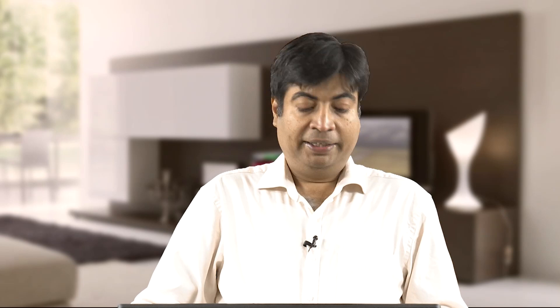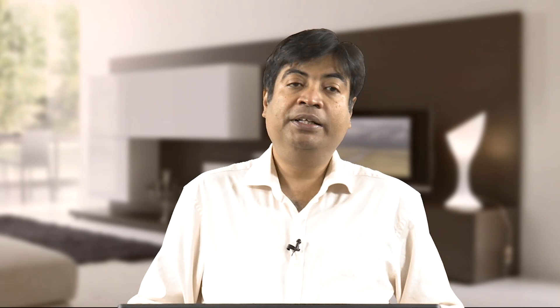The next important aspect of DC microgrid is controllable generation, which provides stable and necessary levels of voltage and frequency. In an AC or hybrid system, frequency must be maintained at every point. In a DC system, you have a DC bus and must maintain its voltage at every point within a tolerance limit. In an AC system, you must maintain both voltage and frequency.